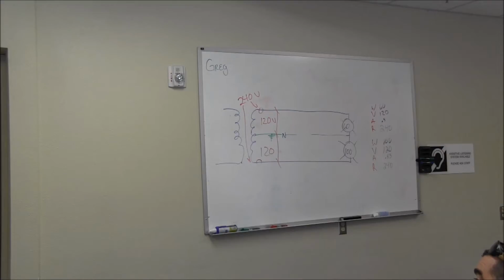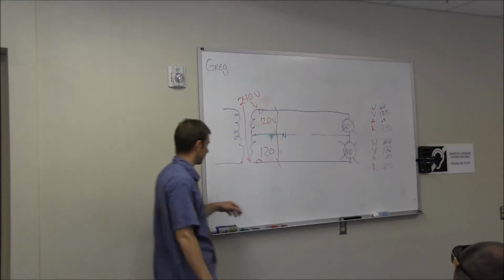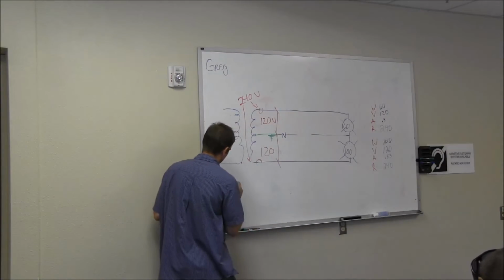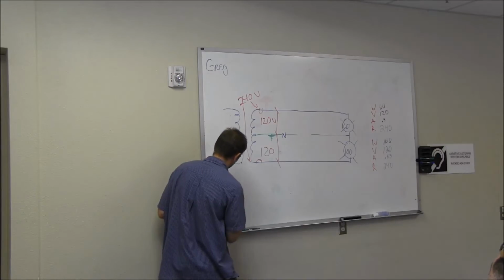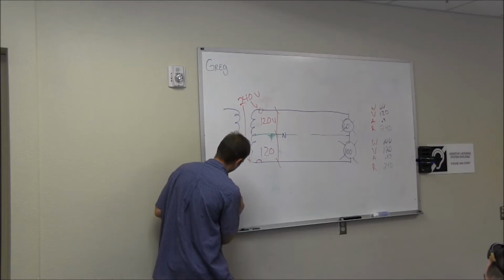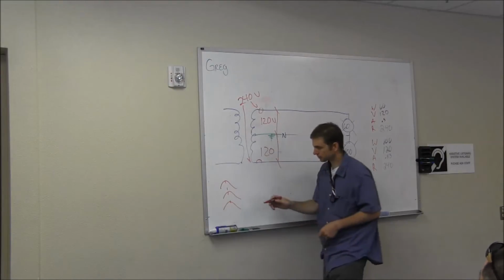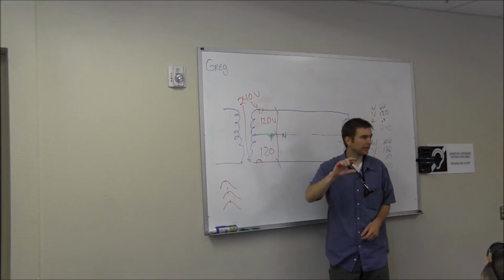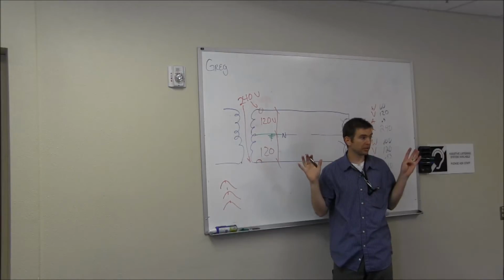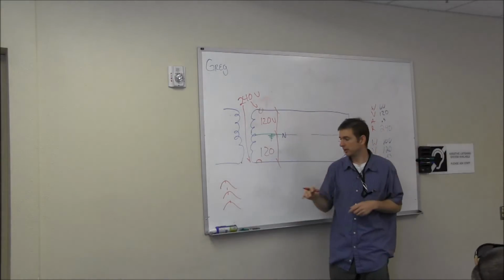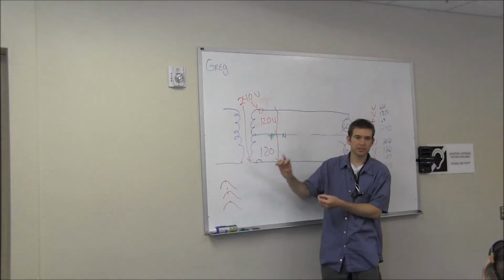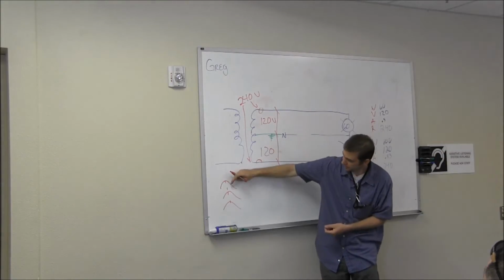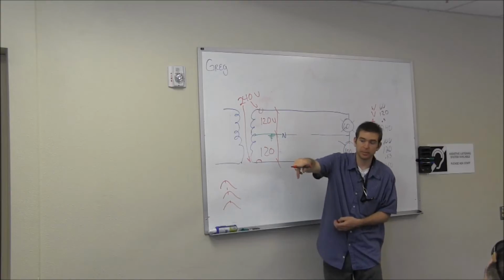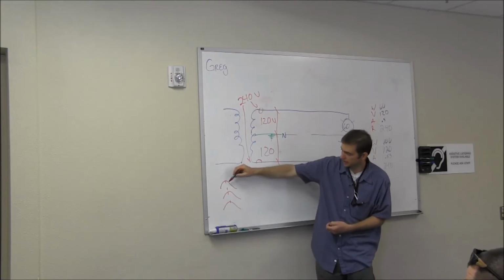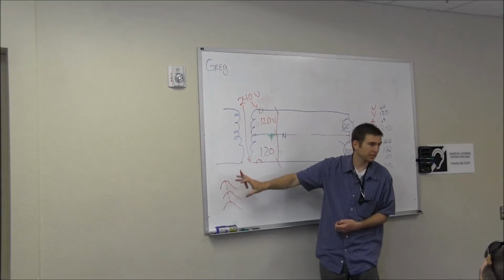Does everyone know what I mean by multi-wire branch circuit? Okay. I don't want to confuse you, so let me explain this. So I have at my circuit breaker, I have 3 circuit breakers in my panel that are interconnected with a breaker tie. Have you all opened up a circuit panel before? Okay, good. So you open up your circuit panel, you're going to see some of those breakers are tied together with a little bar. So this symbol, when you see it in a schematic, whether it's in your plans or in an electrical drawing, this little dotted line here means that these breakers are tied together.